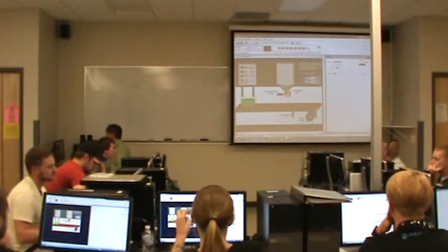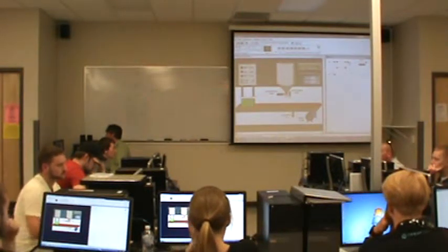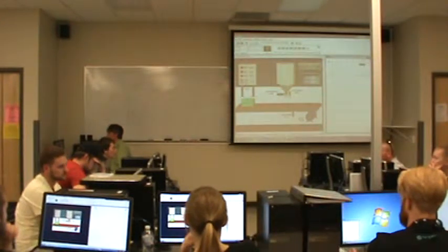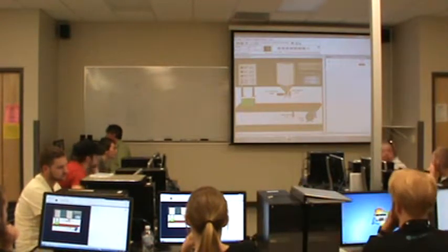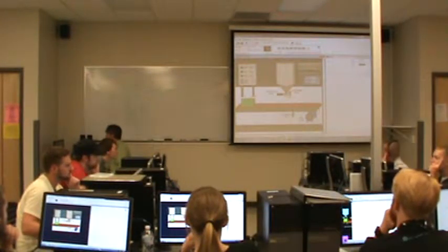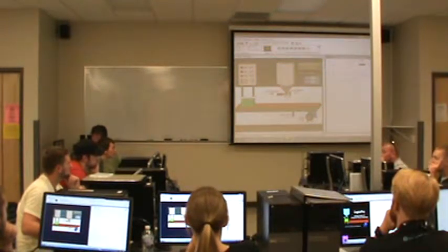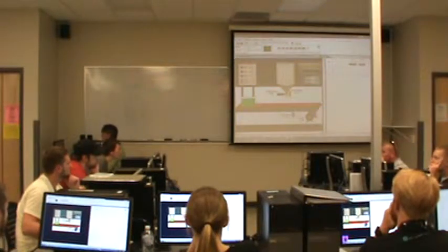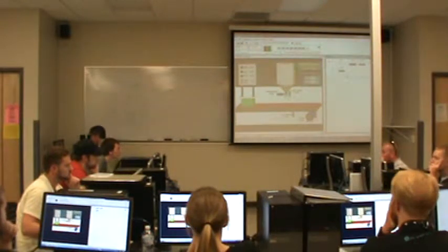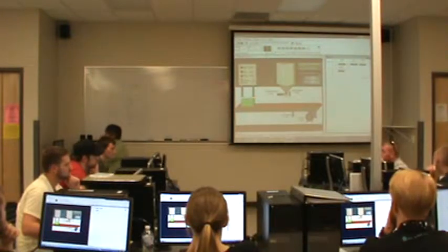I'm going to use an OR around the start button. And since the stop button, as usual, is a normally closed stop button, I need a set of examine if closed contacts. Stop button is here, start button here, and seal-in here.